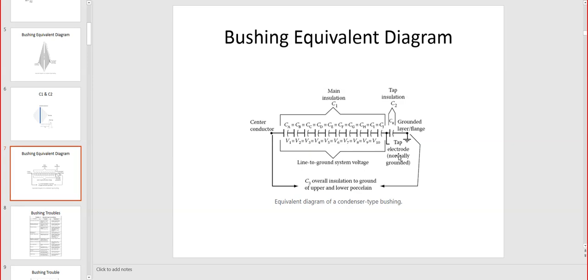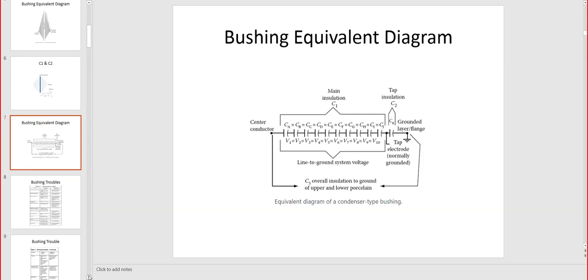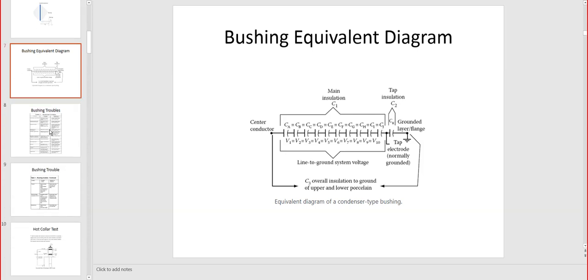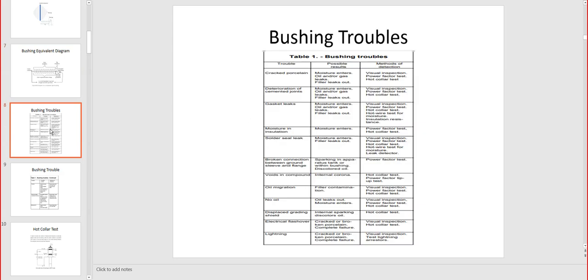Another slide here for pretty much the same thing. You have the C3 overall insulation to ground, and then C1 main insulation of the bushing and tap to the ground, which is the C2. So it's just another representation. Next slide will be the bushing problems. So what kind of problems do we have with the bushing?